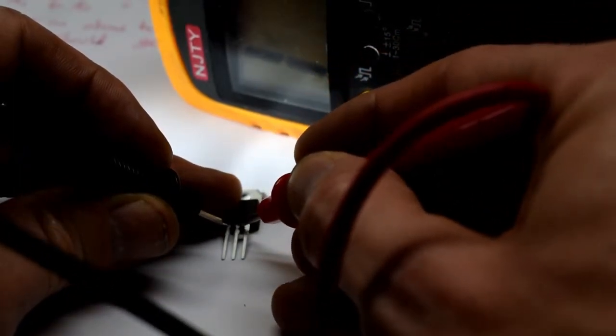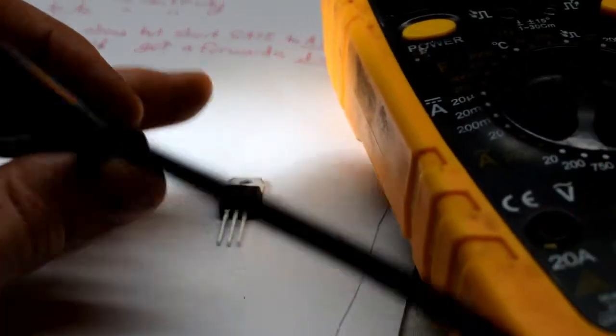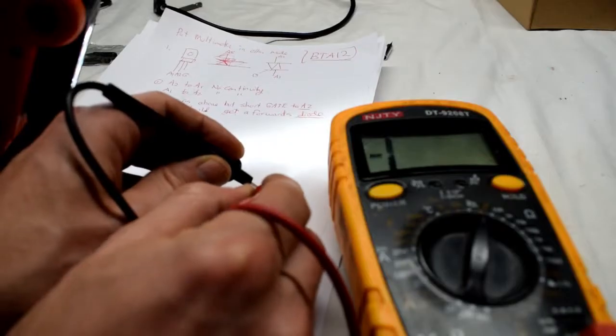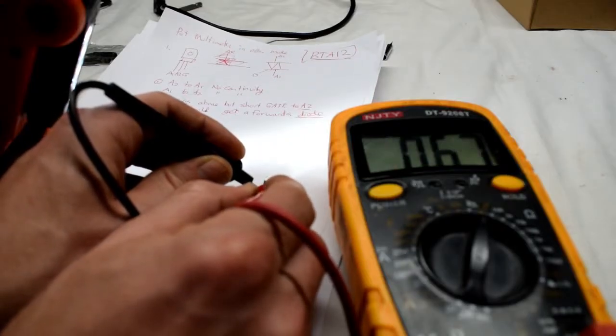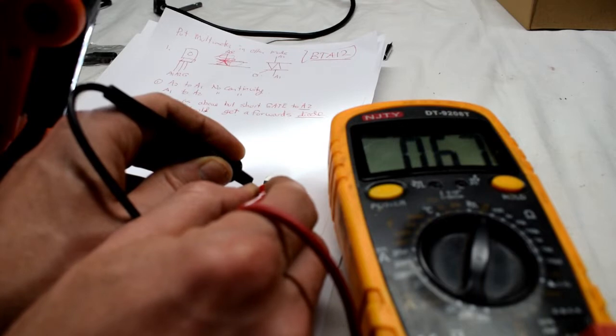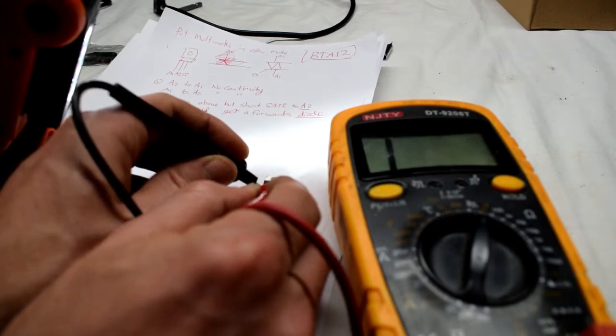Okay, so I have it on continuity mode. Pins 1 and 2 will have an open, so you can see that this is the one. And then 1 and 3, you read about 67 ohms. Alright, 2 and 3, it's open.